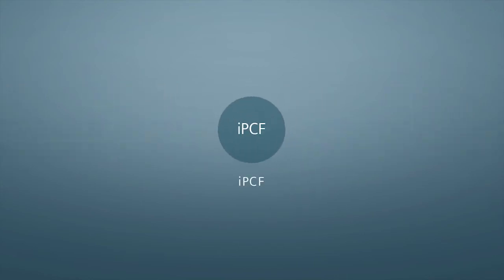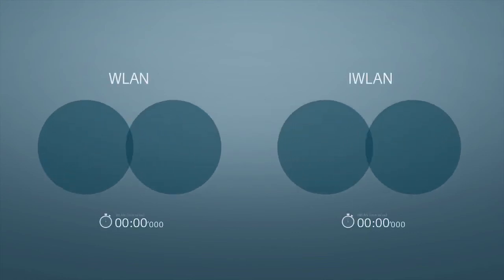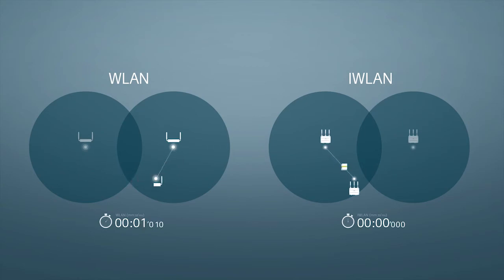In order for a client to be able to change quickly and reliably between two access points, the industrial wireless LAN feature needs IPCF. The IPCF procedure is also called rapid roaming due to its speed. Roaming times are typically under 50 milliseconds, instead of the usual time in the range of tenths of seconds.